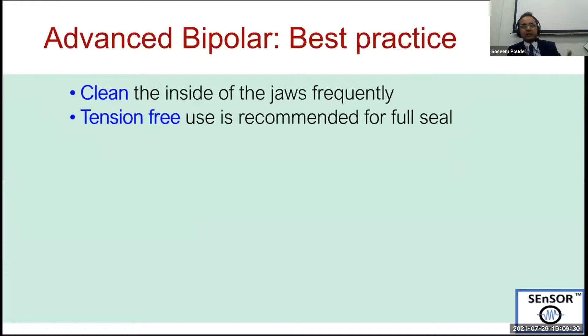And for advanced bipolar, it is better to have it tension free. So if you want a full seal, it's better to use it tension free. And if there is anatomical tension or large vessels, it's also good to have an overlap seal. So you seal it more than once before you fire that mechanical knife to cut. And avoid capturing tissue at the hinge of the jaw at the bottom. That's where you clean it, because it won't seal properly there.